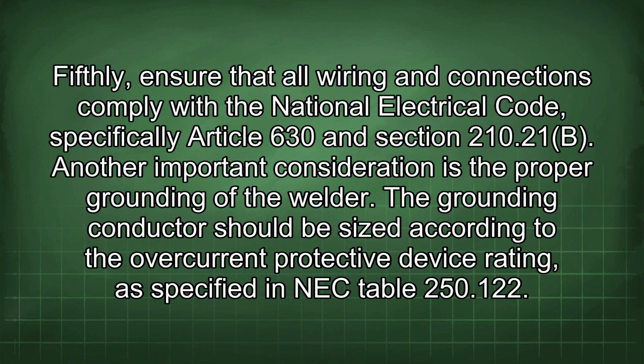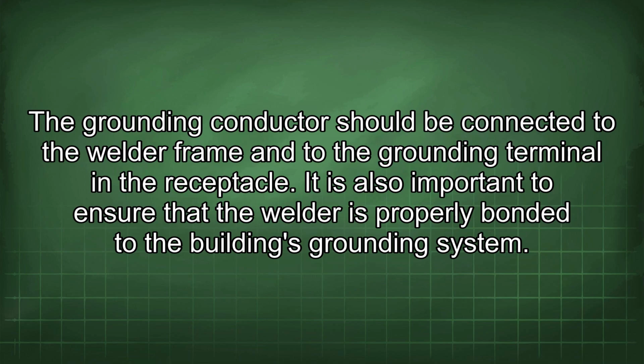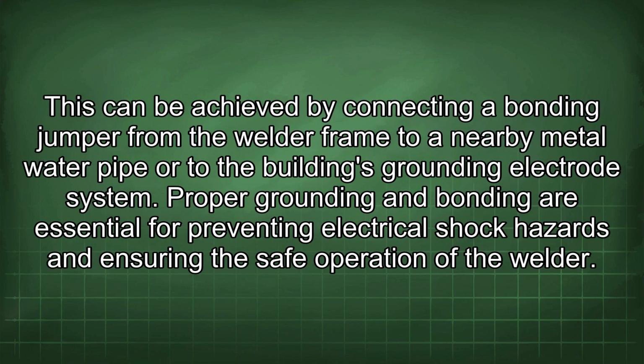Another important consideration is the proper grounding of the welder. The grounding conductor should be sized according to the overcurrent protective device rating as specified in NEC Table 250.122. The grounding conductor should be connected to the welder frame and to the grounding terminal in the receptacle. It is also important to ensure that the welder is properly bonded to the building's grounding system. This can be achieved by connecting a bonding jumper from the welder frame to a nearby metal water pipe or to the building's grounding electrode system.